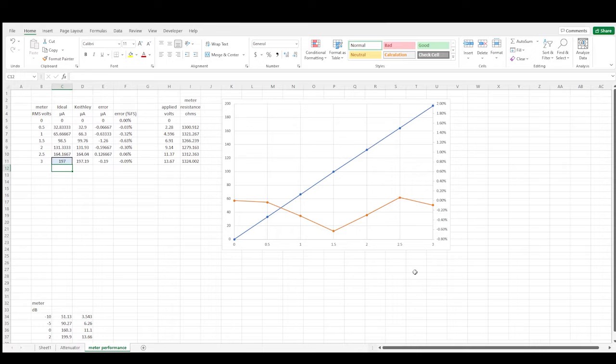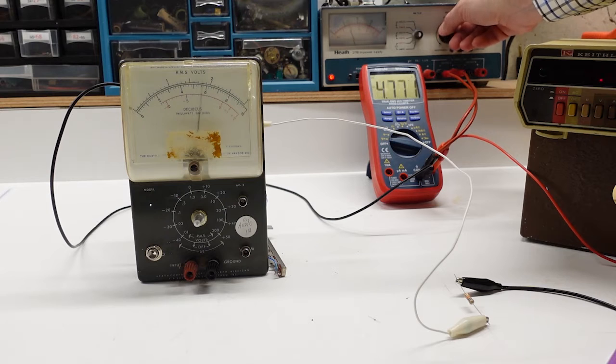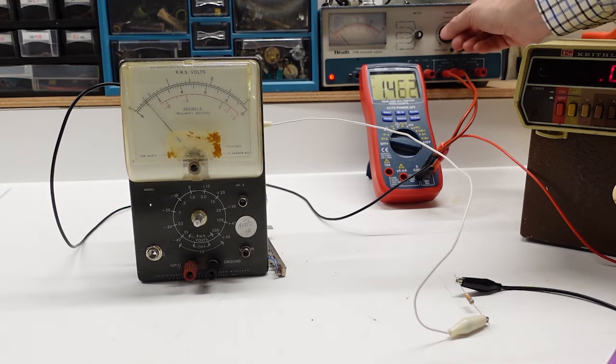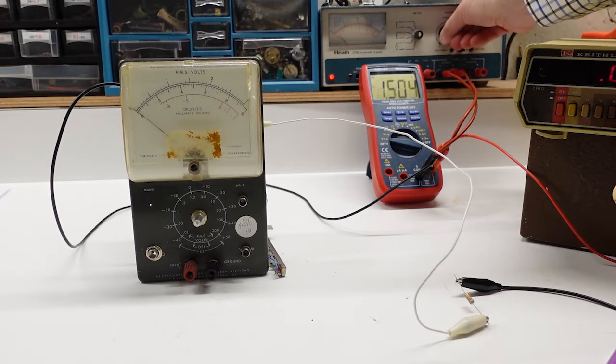So, all things considered, this Simpson meter is tracking plenty accurately enough for this application. The last check for the meter is to see how smoothly it moves. That's easy to do. Just vary the voltage and watch the needle for any sticking or hanging up. Looks like there's no sticking issues, so all in all, the meter looks to be in really good shape.